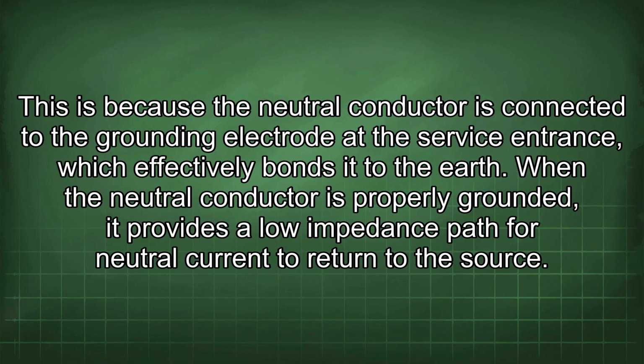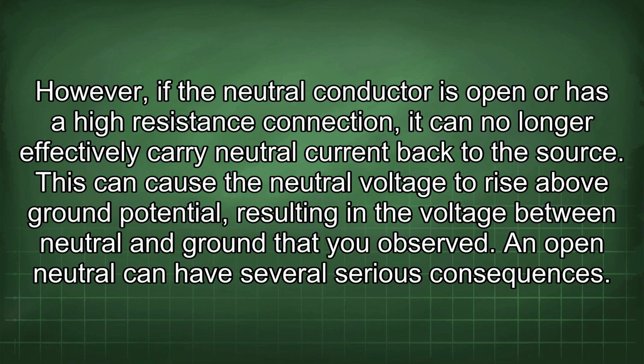This is because the neutral conductor is connected to the grounding electrode at the service entrance, which effectively bonds it to the earth. When the neutral conductor is properly grounded, it provides a low impedance path for neutral current to return to the source. However, if the neutral conductor is open or has a high resistance connection, it can no longer effectively carry neutral current back to the source. This can cause the neutral voltage to rise above ground potential, resulting in the voltage between neutral and ground that you observed. An open neutral can have several serious consequences.